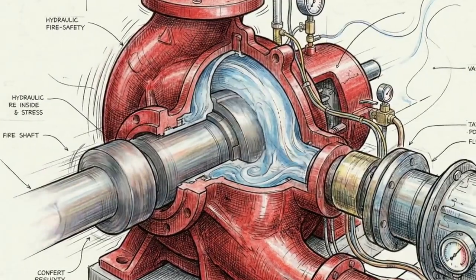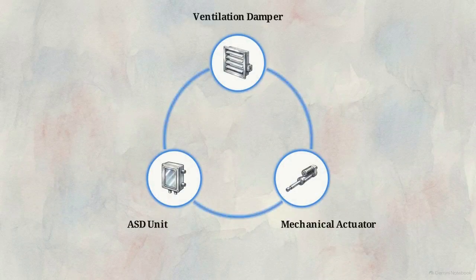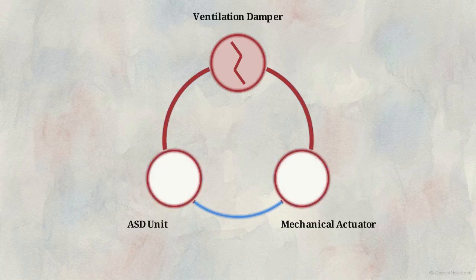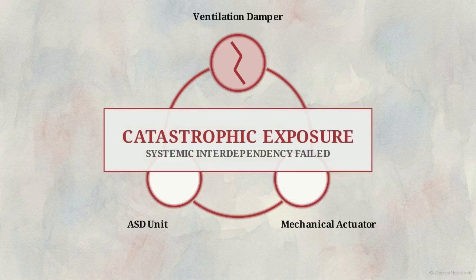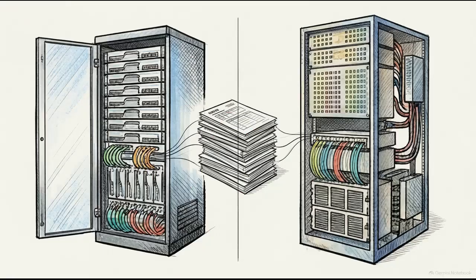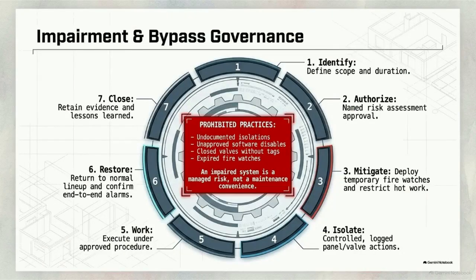High-capacity pumps must be spun up rapidly to prove they meet their hydraulic flow curves without degradation. If any single component in the chain, an ASD unit, a damper, or an actuator, fails its periodic test, the entire facility is exposed to catastrophic loss. Chronological, documented testing is the only proof that the system will perform tomorrow identically to its day one baseline. Human element impairment and unmanaged bypasses represent the most significant threat to a fully commissioned facility.